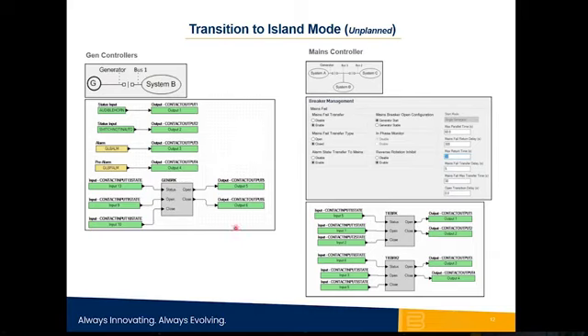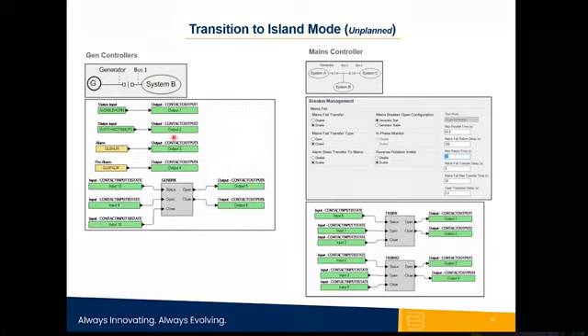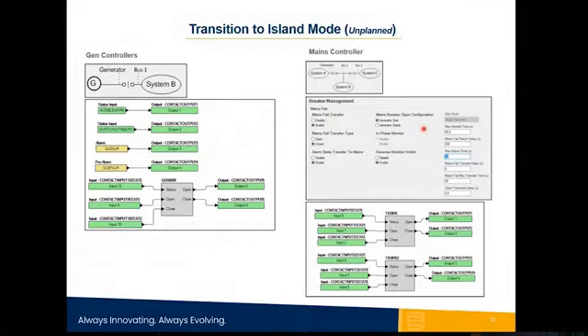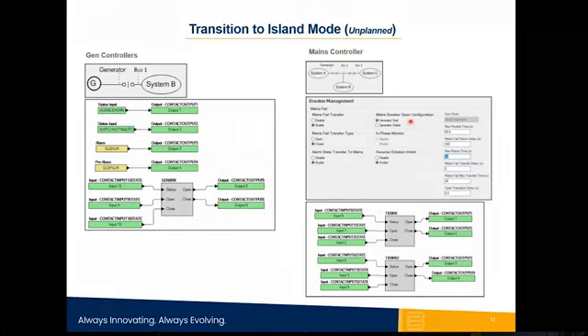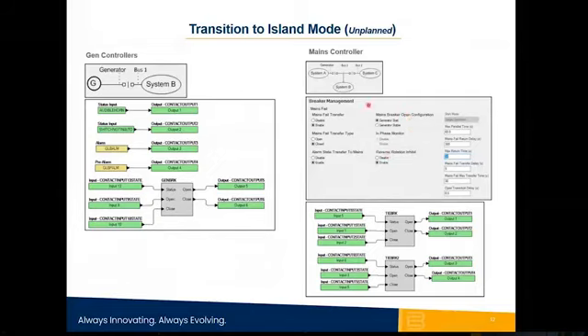So this is the default logic scheme in a 2020 HD, where you just have some annunciations and breaker control. In the mains controller, which is doing more of the work in a sense, you'd want to enable mains failure transfer. And all these settings here are going to achieve your automatic transfer function. So transferring to generator power upon sensing a dead mains, and then transferring back to the utility, the 2020 HD that's connected to the mains, sensing the mains and controlling the mains breaker, is going to perform that function.